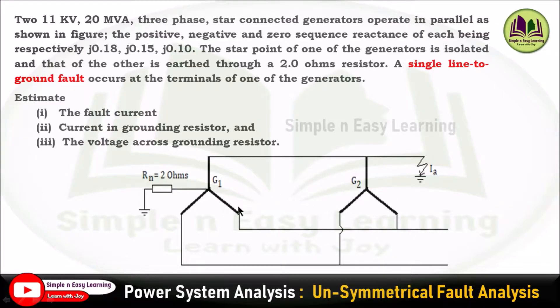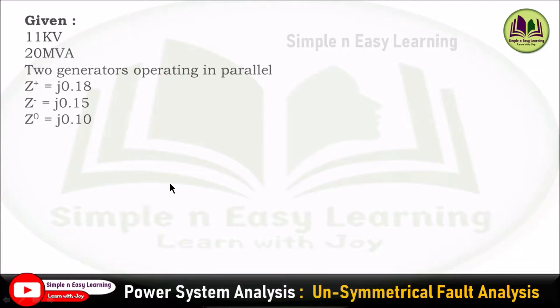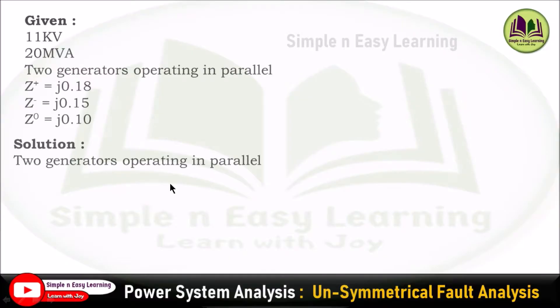Two generators are connected in parallel, and the neutral point of one generator is connected to ground through a neutral resistance of 2 ohm. Given data: 11 kV, 20 MVA, two generators operating in parallel. Positive sequence impedance is J0.18, negative sequence impedance is J0.15, and zero sequence impedance is J0.10. We are going to find the sequence impedance and draw the sequence network for all three sequences.